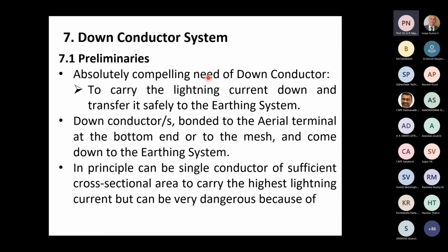The whole principle of protection against lightning is to provide a convenient, safe path for the lightning current to go to ground, because lightning will ultimately always go to ground. That's where the positive charges are, induced by the cloud. So this negative current flows into the ground and neutralizes the positive charges induced on the earth surface, as was discussed in the first webinar itself. This is unavoidable. Lightning current must enter the ground. So if we provide a safe path, we have done our duty and met our target. So it's absolutely compelling to have a down conductor. What's the purpose? To carry the lightning current down and transfer it safely to the earthing system.